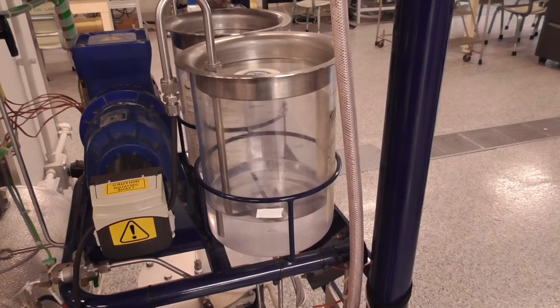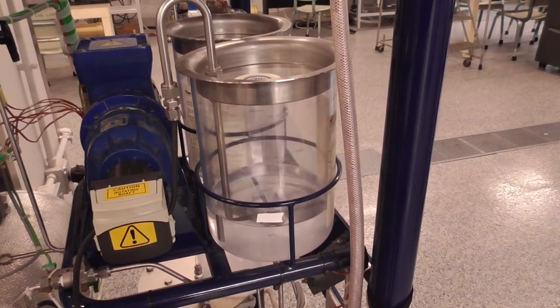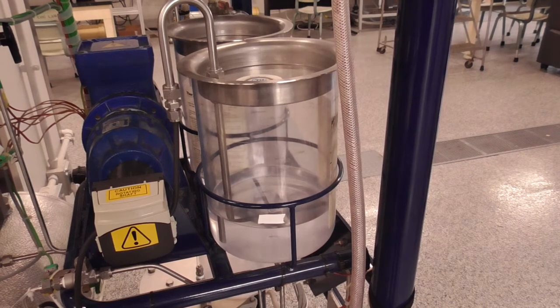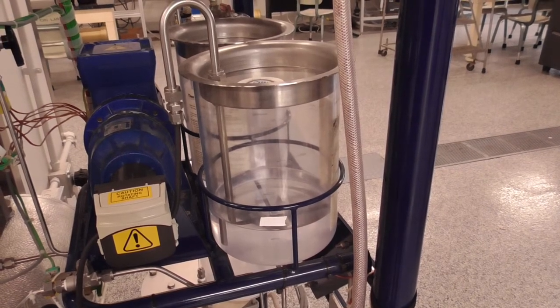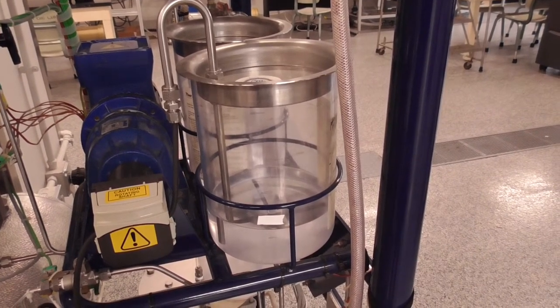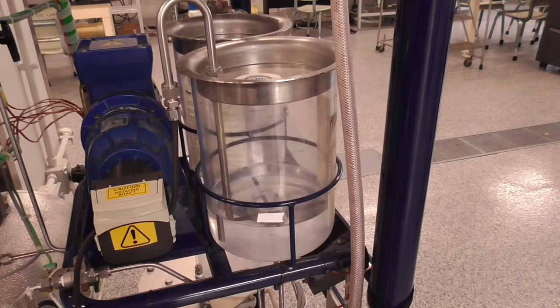One word of caution on feed: it sometimes gets a vapor lock in the tubing and does not pump. And so it's good to mark it with labeling tape or a Sharpie so you can ensure that indeed the feed is going down and being fed to the column.